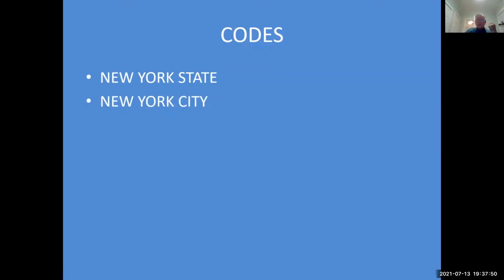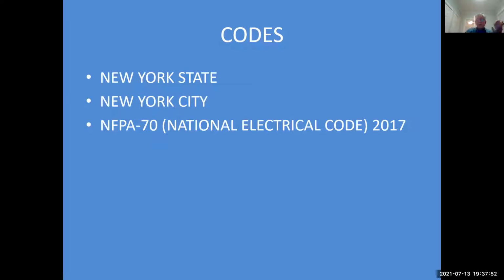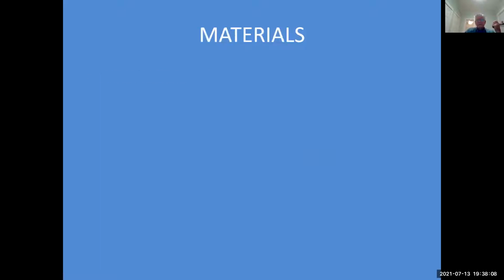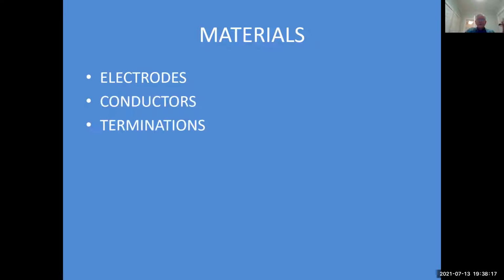There are codes that require certain degrees of grounding. New York State has codes, New York City has codes. The NFPA 70, which is the National Electrical Code, has probably the largest section in that code on grounding. And local codes: each town and village may have their own requirements, especially if you have towers. The important materials that you'll be involved with in grounding will be your electrodes, the conductors, and the terminations.